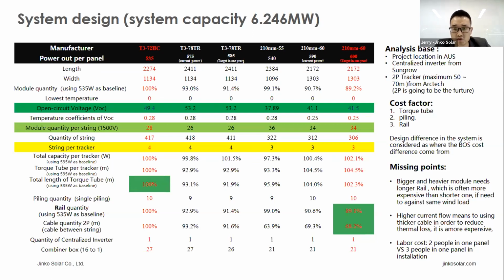Yes, 210 modules have advantages - we use 32% less cable than 182 solar modules. But if you put safety factors into consideration, you have to purchase the home run cables with thicker, larger cross-sectional area. That means the cable needs to be longer and thicker, so that also means more cost.